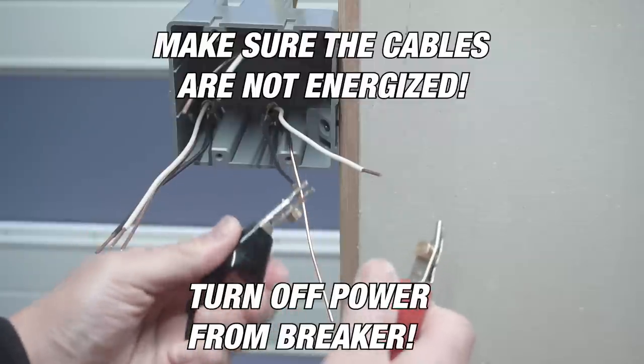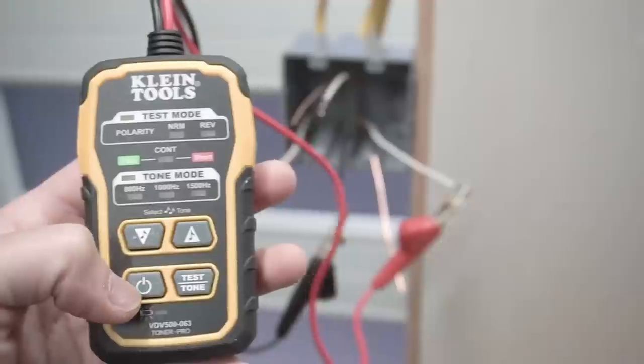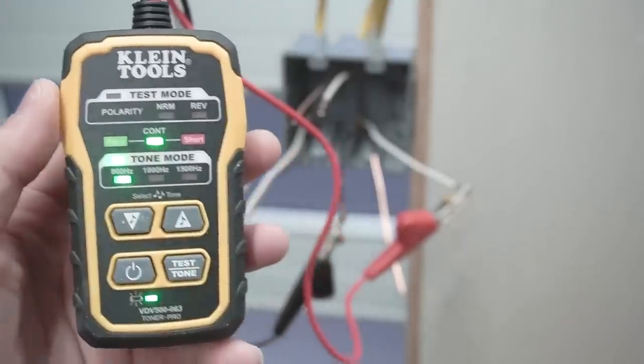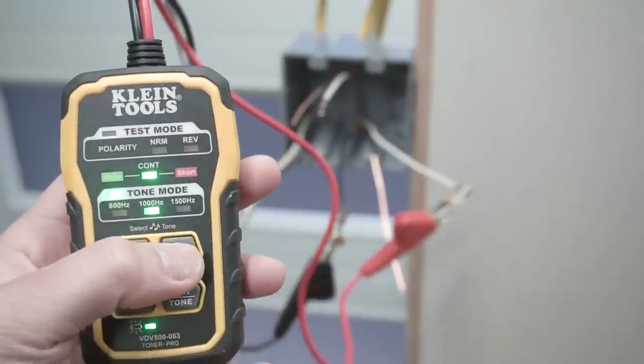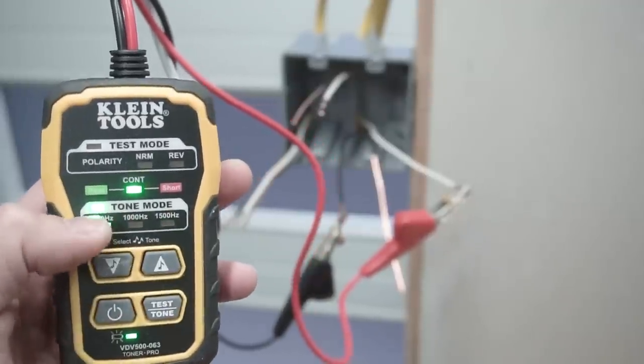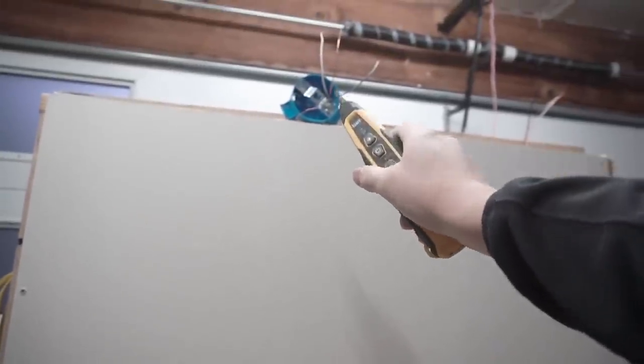Let's try to do your best to group up all the wires to their respective cables. You can see the sleeve where they're actually going to. That's even perfect. Now you know where they're actually grouped up, and that's half of the battle. Attach it to the bare wire. So I'm just going to attach it right there, and then attach it right there. What you can do now is just turn on the device. So once it says continuity and it's green, then you're ready to go. And it actually defaults to 800 hertz, but you can scroll around there and pick whichever tone that you want. But we're just going to stick with the default. You can control the volume levels.